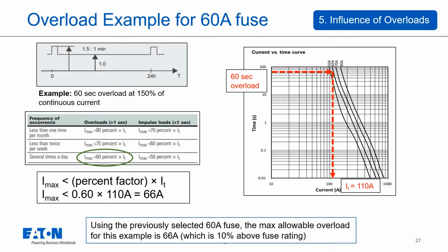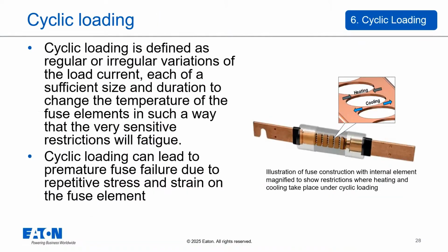This brings us to another factor affecting fuse life, cyclic loading. Cyclic loading means the current isn't constant. It varies regularly or irregularly. These variations cause the fuse element's temperature to constantly change. Repeated heating and cooling, particularly at the restrictions or narrow points of the element, can cause metal fatigue over time. Think of bending a paperclip back and forth. Eventually, it breaks. This repetitive stress from cyclic loading can lead to the fuse failing prematurely, even if the current never reaches levels that would cause it to blow immediately.